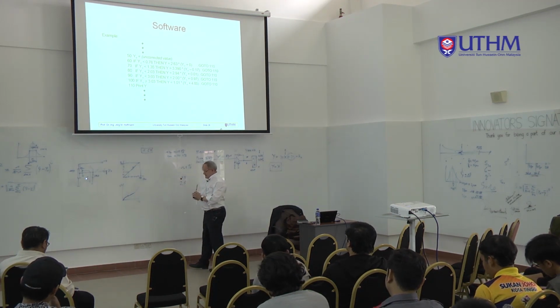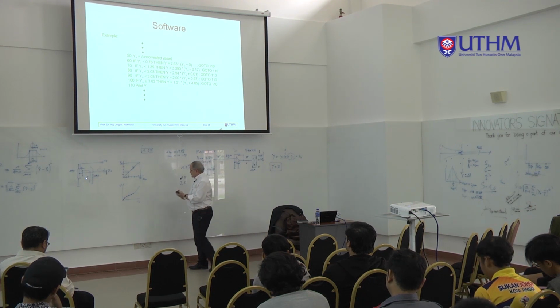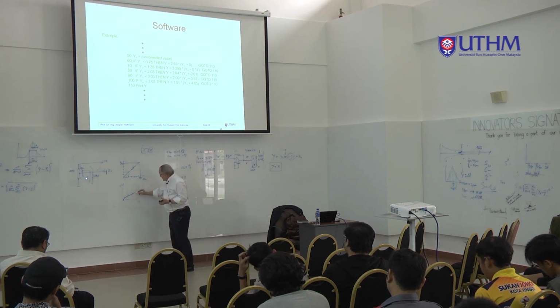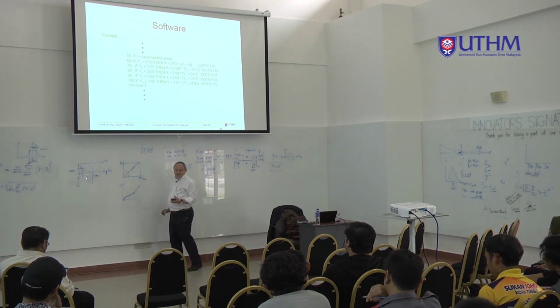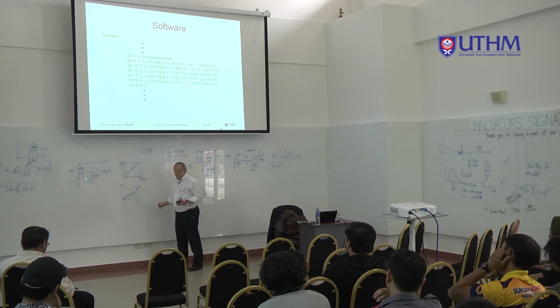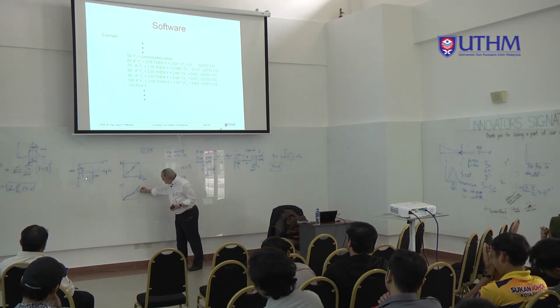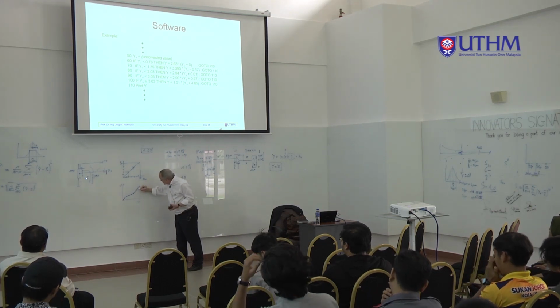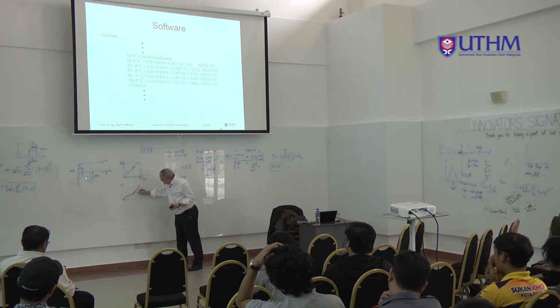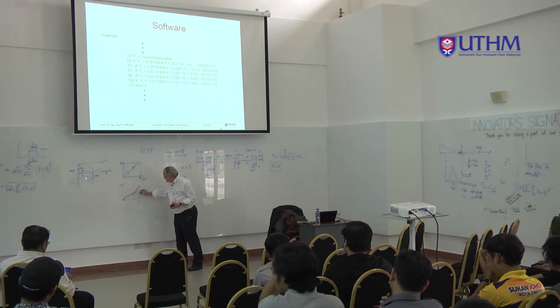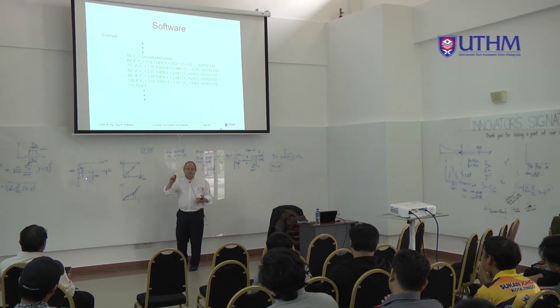When the interval is too big, for example if you have a calibration point here and another point here, and that is too wide, of course you get an error. But then you have to put additional points in, so that you can calculate it step by step.